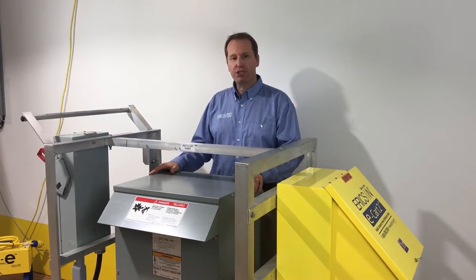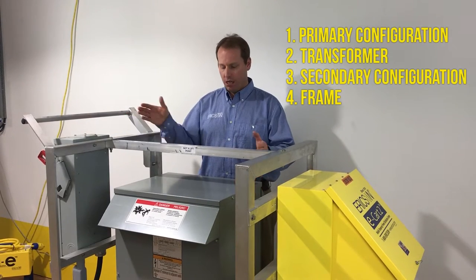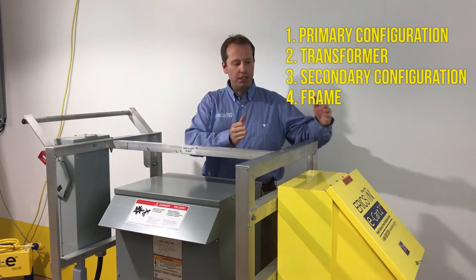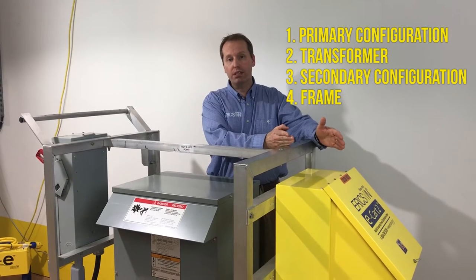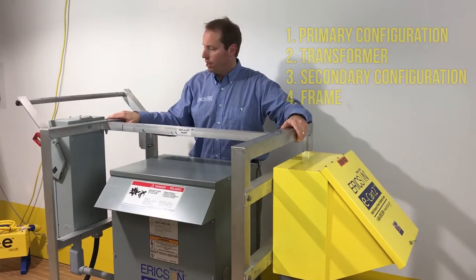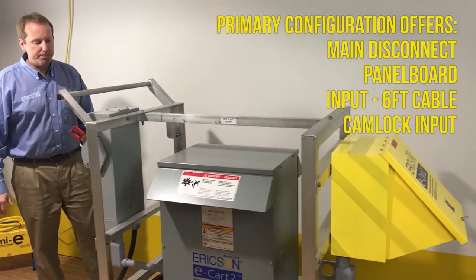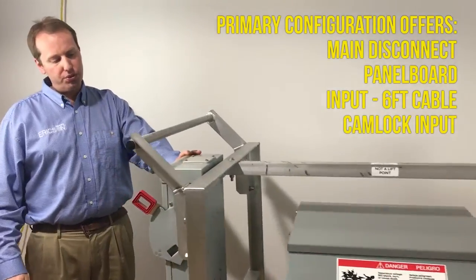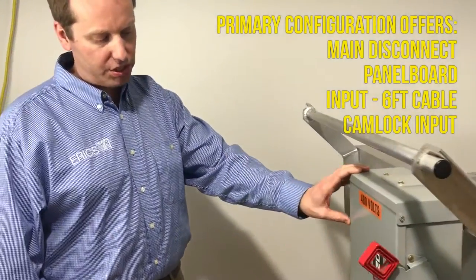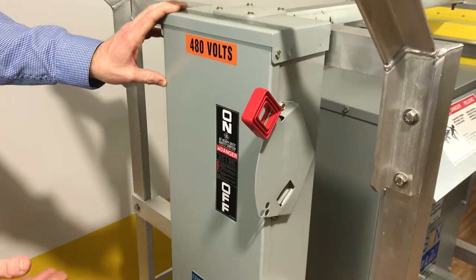This cart is comprised of four major areas: the primary input side, the transformer, the secondary 120-240 single phase or 120-208 distribution side, and the frame. Let's talk about the primary side. Our standard input comprises of a fused, safety, heavy-duty main disconnect switch with a six-foot piece of power cable and bushing.